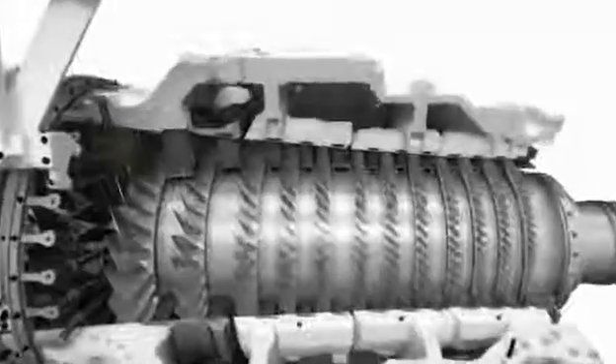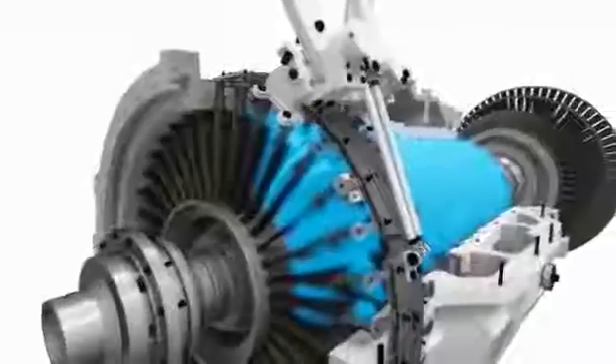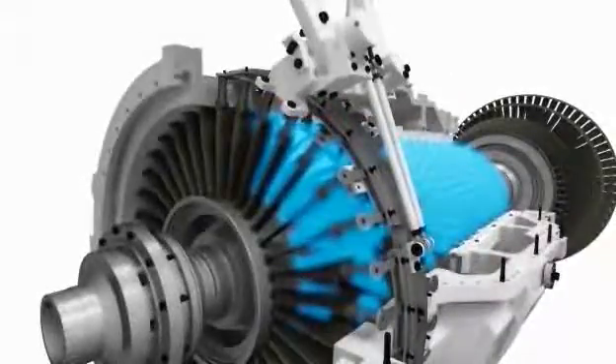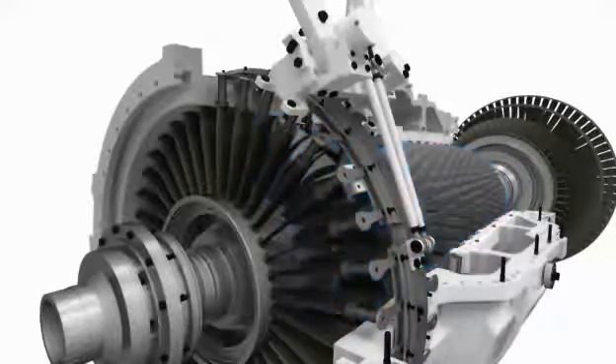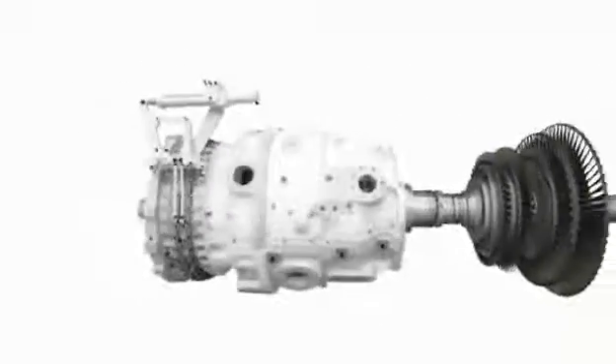The compressor is a 13-stage axial flow compressor with a 24-to-1 pressure ratio. It offers a controlled diffusion airfoil for high efficiency and 2 variable guide vanes for optimized performance, even in the most extreme conditions. The combustors are the 4th generation of DLE burners from Siemens.